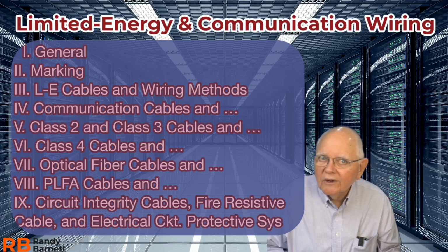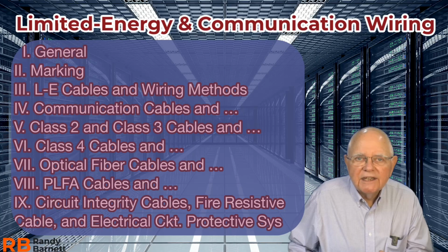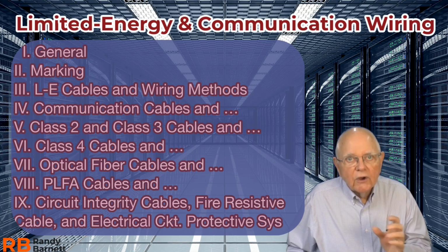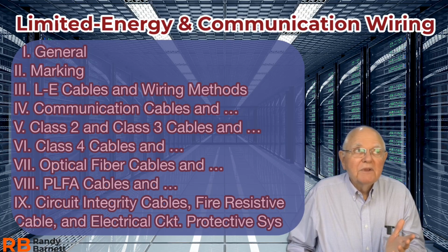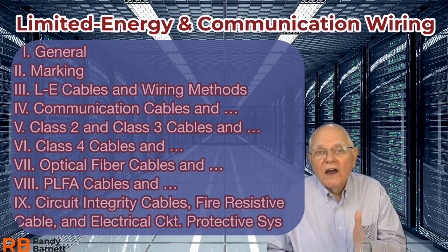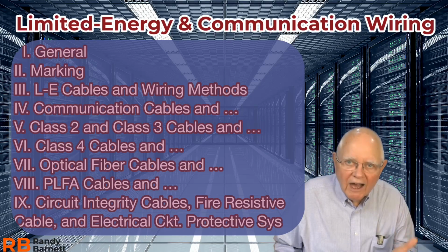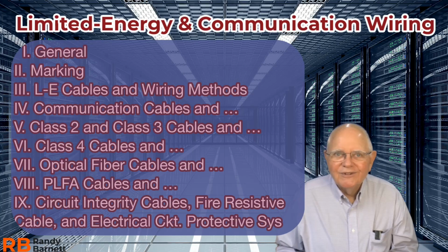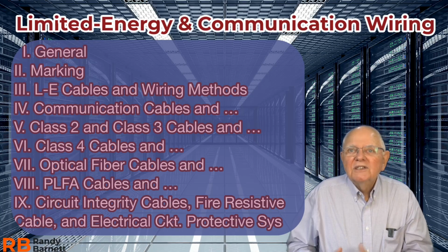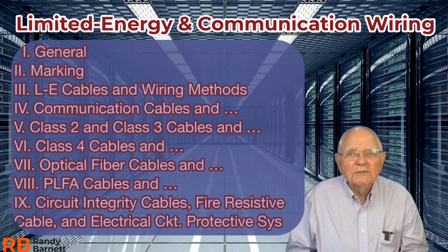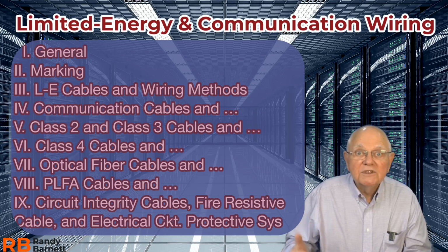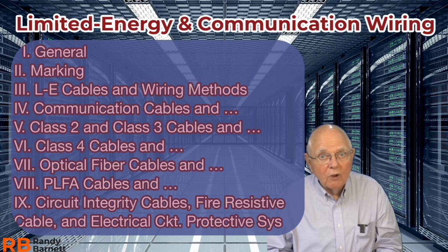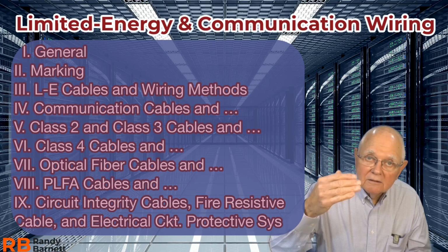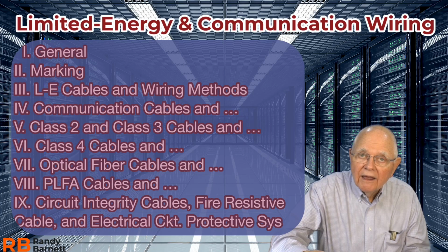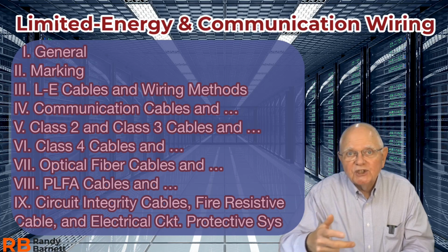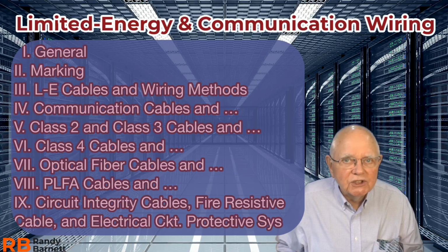Oh, that could be important, huh? OF, anytime I see OF, I'm talking optical fiber. So OFN is an example. The table tells me that's optical fiber or non-conductive optical fiber general purpose cable, righty? Now, for each of the remaining parts throughout the article, you're going to find specific installation requirements for the particular cables. So take a look at the table and see what type of conductors you're allowed to run, and then go to the particular section to find out any specific installation requirements you need.